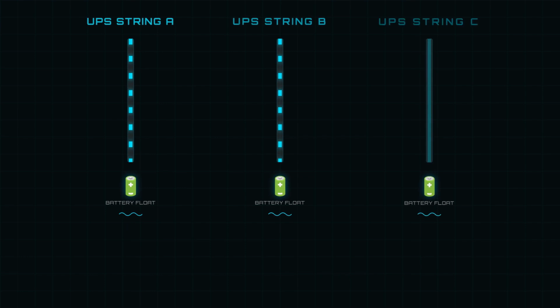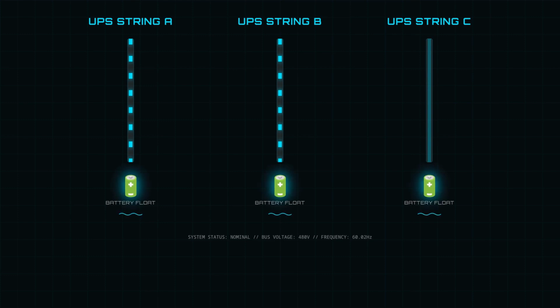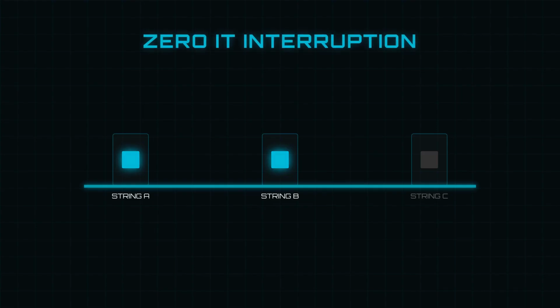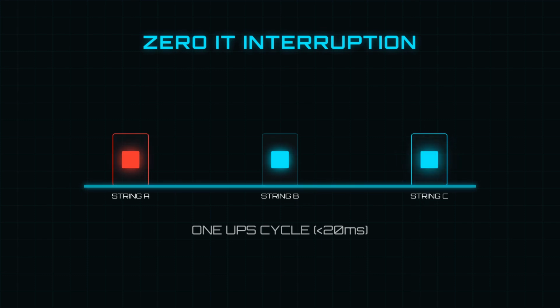Each data hall has its own 2N+1 system. 3 independent strings, A and B, share the load 50-50. The C string is on hot standby, fully energized, battery float charged, but carrying no load until it is called upon. The C string is ready to pick up the full hall load within a single UPS cycle, less than 20 milliseconds, if either A or B fails. This architecture ensures zero interruption to our critical IT infrastructure, regardless of individual string faults.